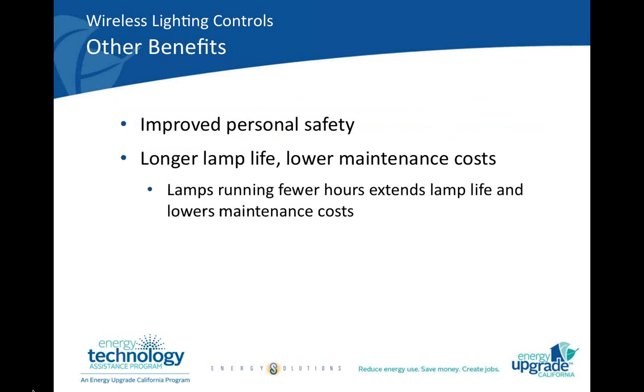So some of the other benefits, like bilevel lighting, that come along with wireless lighting controls are increased personal safety, and also longer lamp life and lower maintenance costs over time. Like touched on briefly in the bilevel section, one of the advantages of having a wireless lighting system is that you can see the system's performance in real time from a desktop computer. So you can see if you have fixtures that are out, you can see what fixtures are at what light level. You can reprogram them from this interface, all without having to actually go to the physical location and check the lamps on a regular basis. So by doing that, you can save quite a substantial amount in maintenance savings. Next slide, please.